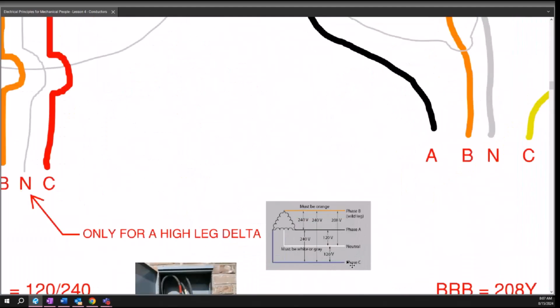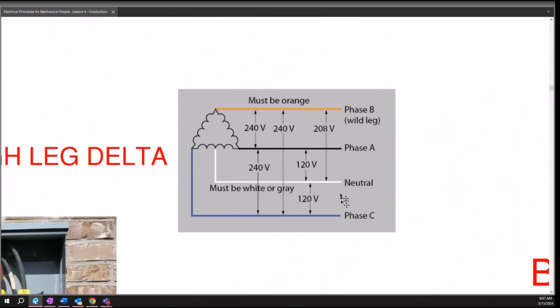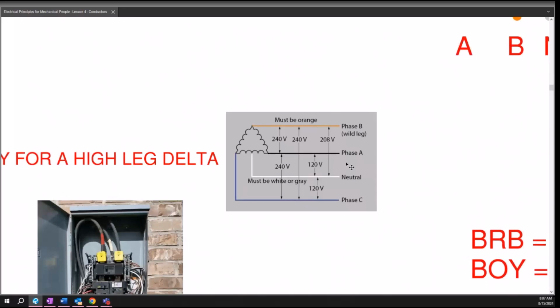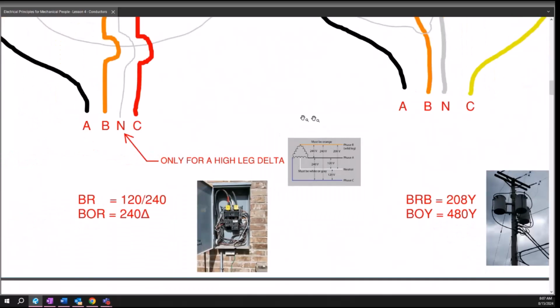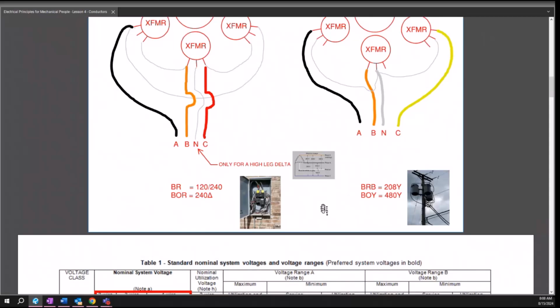And what that looks like this, and the reason a high leg is so dangerous is because whenever you install, say, receptacles, for instance, a receptacle is supposed to have 120 volts. Well, on A to neutral and C to neutral, you do have 120 volts. But when you put a breaker on B phase, you've actually got 208 volts, and that'll destroy pretty much anything that you put in there, like a lamp or something, that's going to tear it up. So that's why you've got to be very careful with that. And I'll show you what a panel looks like here in just a second.